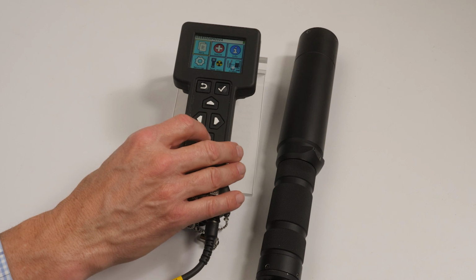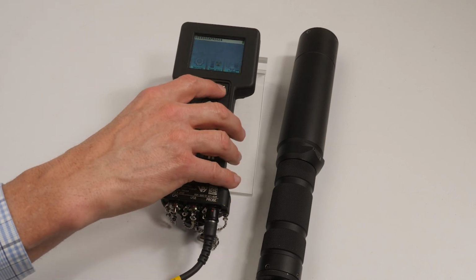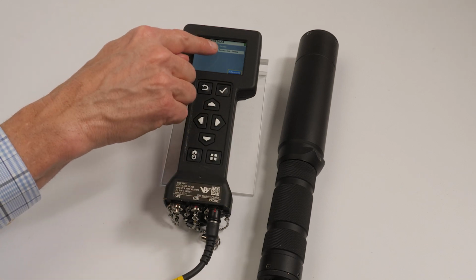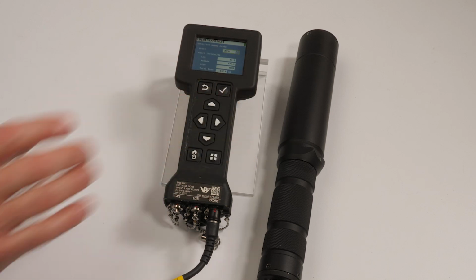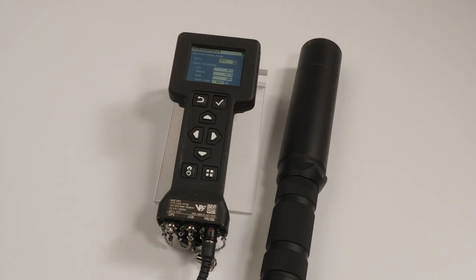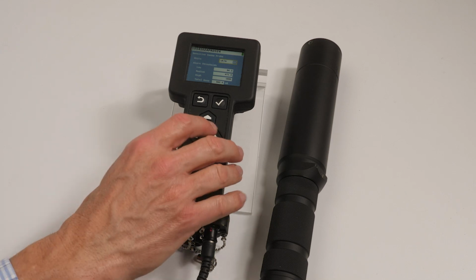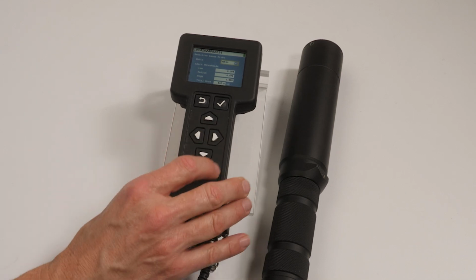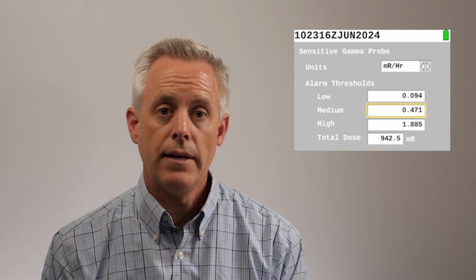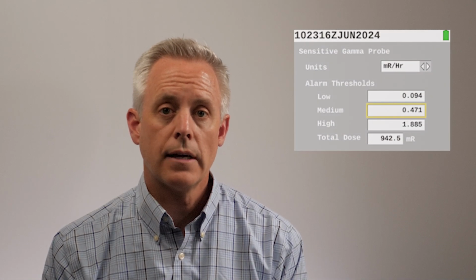There are probe-specific settings you can change for the sensitive gamma probe. To access those settings, press the menu key, highlight Probes, press Enter, highlight the sensitive gamma icon, and press Enter. There is only one channel for the sensitive gamma probe, so you can't change the channel. Press the Enter key to access the Advanced Sensitive Gamma Probe screen. Change the units of measurement by using the left and right arrow keys. Press the down arrow key to highlight low, medium, high, or total dose alarm threshold values. Threshold values are specific to the unit of measure set at the top of the page.